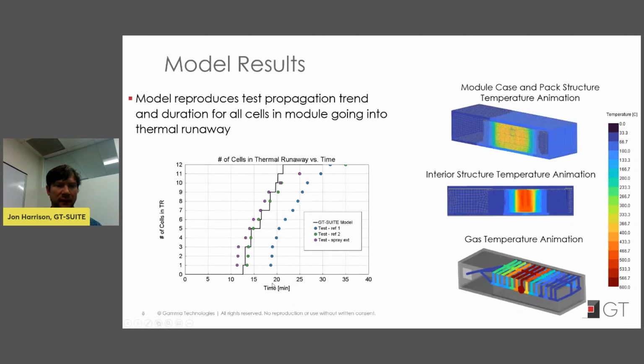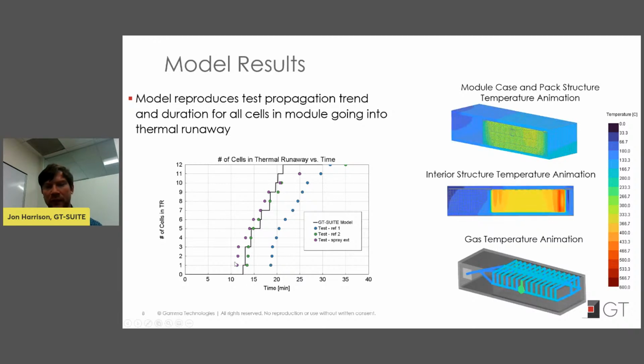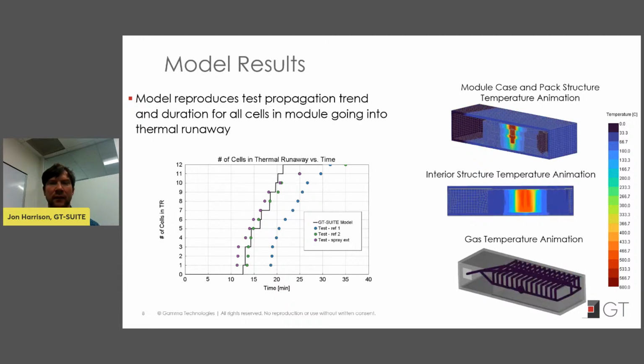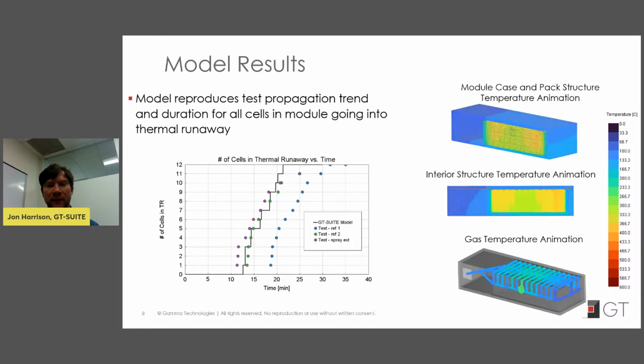And so in this case, you could see there's a couple tests that were run physically, and the time at which they went into thermal runaway was different due to the way it was heated, but the trend and the duration it takes for all the cells in a given module to go into thermal runaway is replicated just like test. And so from there, that allows you to do model extrapolation to test, okay, what if I change the materials between cells, or what if I change the pack structure itself, or investigate different fire suppression strategies? How does that influence how this thermal runaway will go forward?